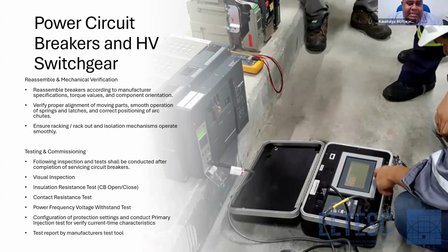Following that, inspection and testing shall be conducted after completion of servicing the circuit breaker. First, a visual inspection by a competent person. So you have to check for any residues, any oxidation present. Then you can proceed with the insulation test, mainly at closed position and open position. That means the switchgear at open position and closed position, between phases and top and bottom. At open position, top and bottom, closed position, between phases and neutral. Thereafter, with the body, because the chassis of the ACB is metal, and you have to check with the chassis also.